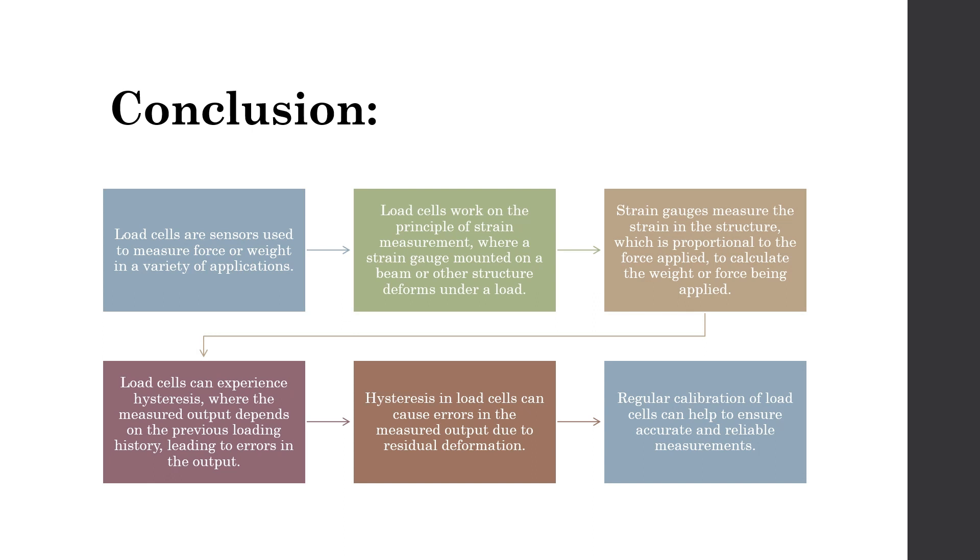Load cells are basically sensors that are used to measure force or weight and they have a variety of applications. Load cells work on the principle of strain measurement, where a strain gauge mounted on a beam or other structure deforms under a load. Strain gauge measures the strain in the structure, which is proportional to the load being applied.